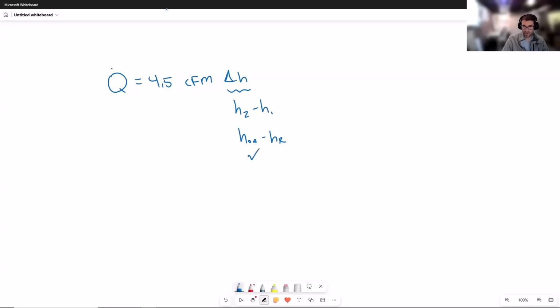Both of these are fully defined. We can identify both of those. If we know the CFM, we can find the total cooling load. The reason I had to give you the number of occupants was because the CFM was not fully defined at the beginning of the problem. The CFM was partly dependent upon how much ventilation air needed to be introduced, and that's a function of the occupants. So that's why I told you the type of space and the number of people in the space, so that we had a way to come at that CFM.